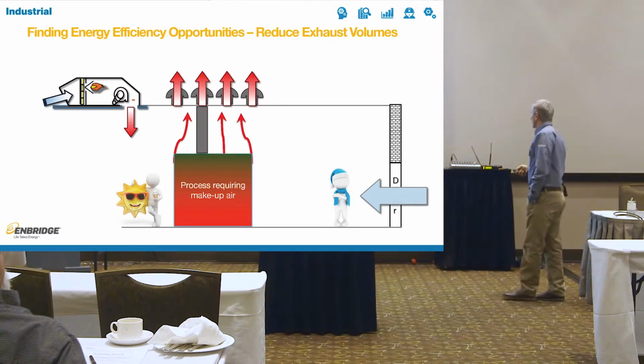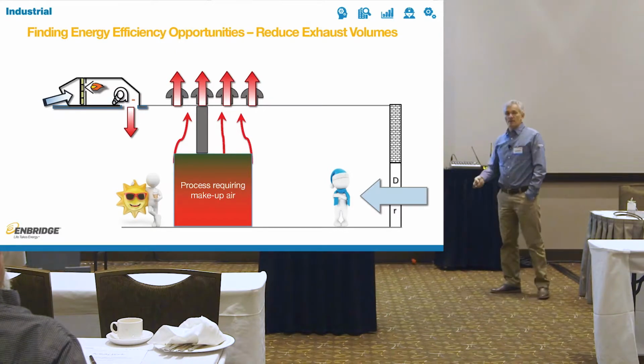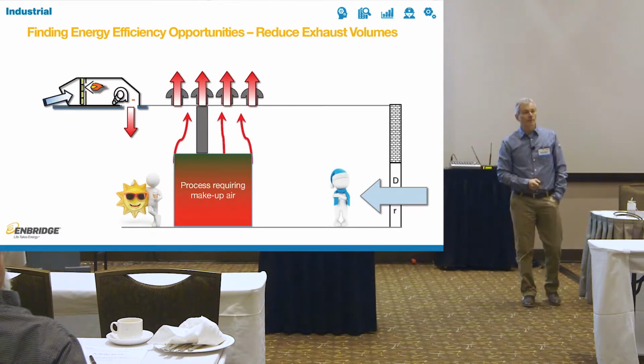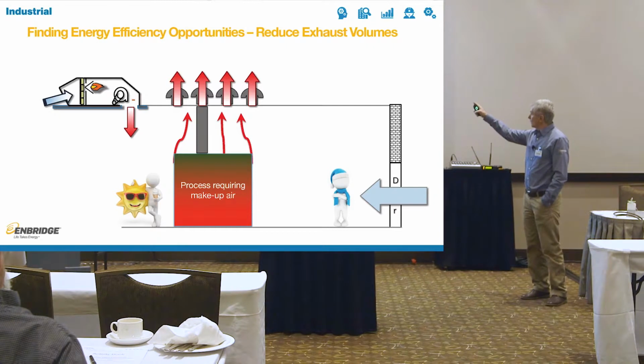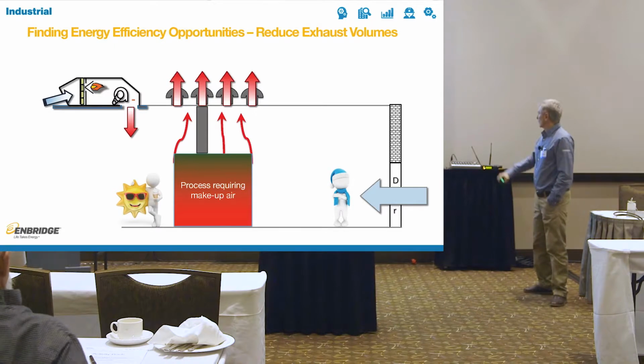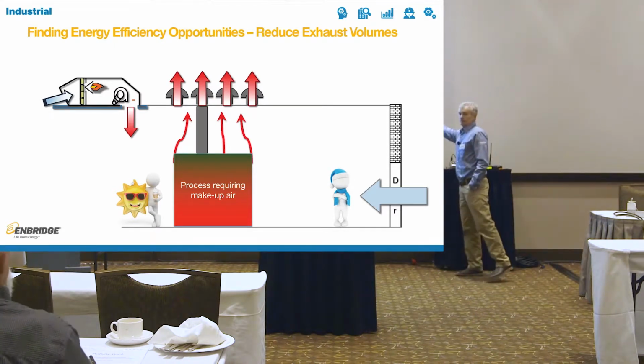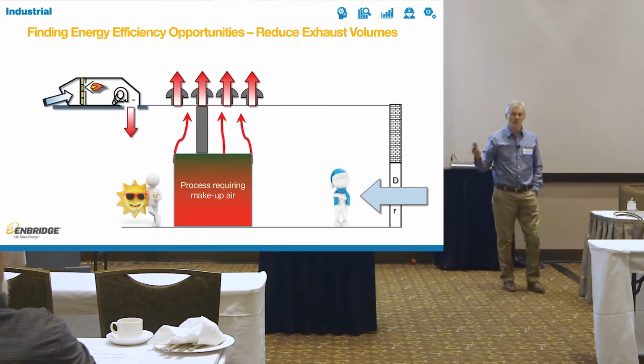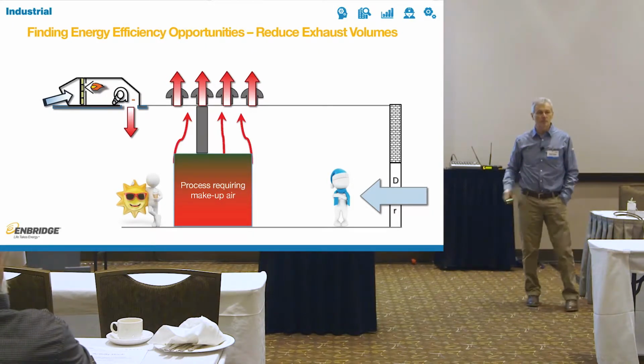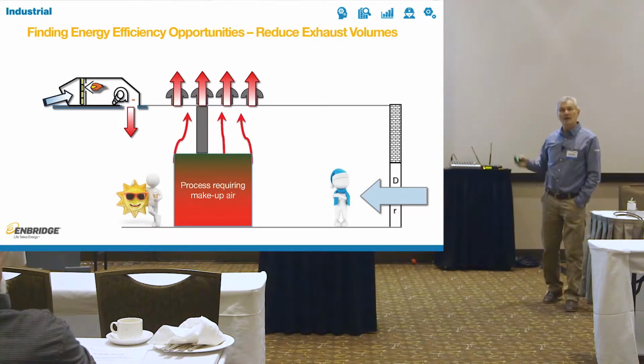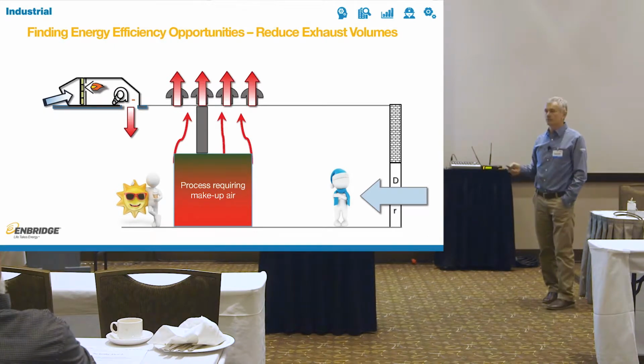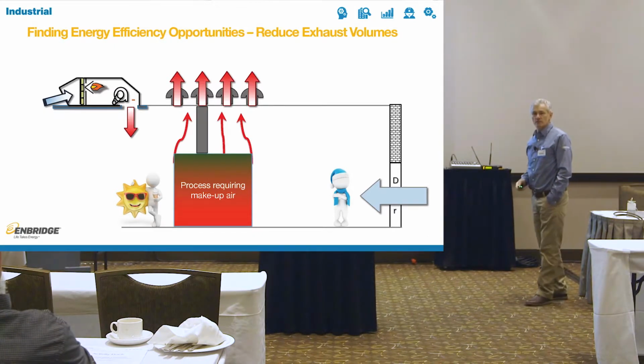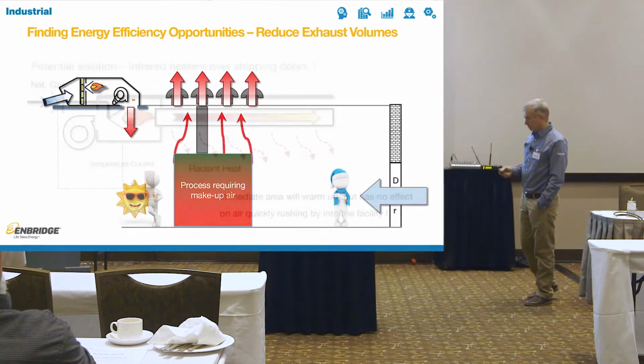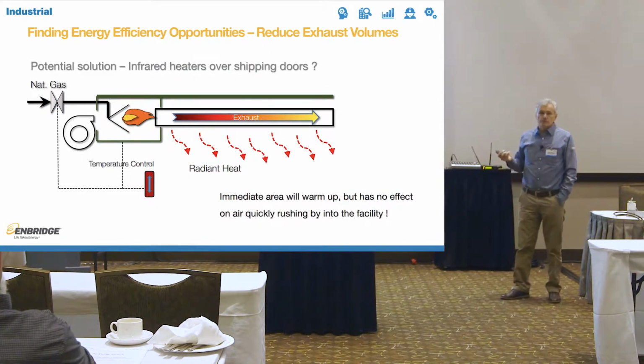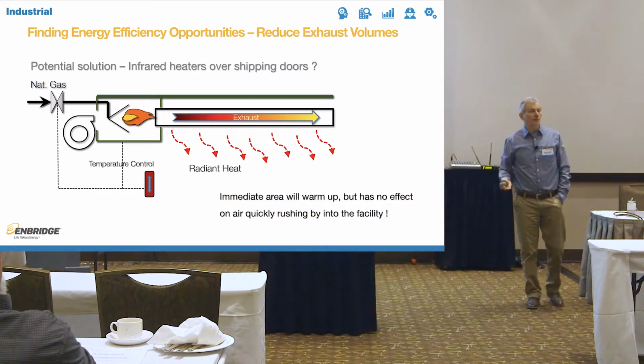So the problem, of course, comes when March rolls around again, or January. All those exhausts. See how only one out of those 4 arrows is balanced by the makeup air? Well, the rest comes from here. We all like to blame shipping doors, but really it would come from anywhere. It just wouldn't stop. You can close that shipping door, it would come from somewhere else. And it would be cold air because you're not preheating it. So the guy at the shipping area is freezing. So what do we do? We start investigating how to heat the guy at the shipping area.